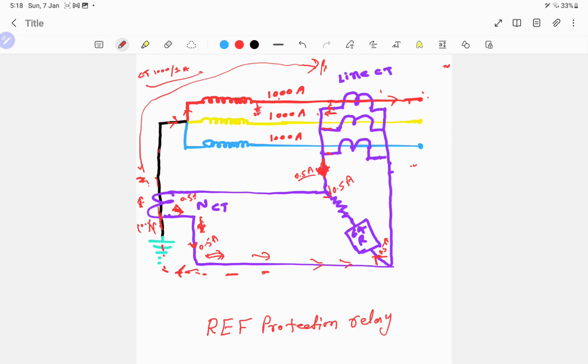Now if the fault occurs here, the fault current will flow from the red phase winding through the earth fault towards the ground, through the neutral CT towards the source, back to the R phase. So the resultant current here will be 1000 amps because the fault occurs here. The load current here could be 1500, but 500 amps will go towards the ground and the resultant current here will be 1000 amps. So 1000 amp, 1000 amp and 1000 amp in all three phases.